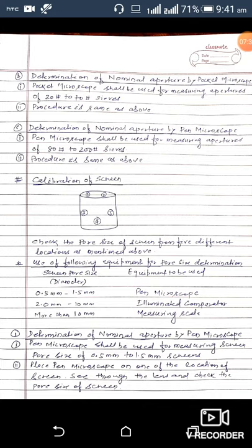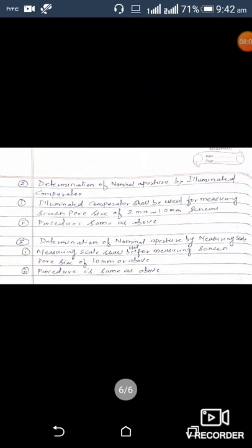Determination of nominal aperture by pen microscope: the pen microscope shall be used for measuring screen pore size of 0.5 mm to 1.5 mm. Place the pen microscope on one of the locations of the screen, see through the lens, and check the pore size. Determination of nominal aperture by illuminated comparator: the illuminated comparator shall be used for measuring screen pore size of 2 mm to 10 mm, and the procedure is the same as above.